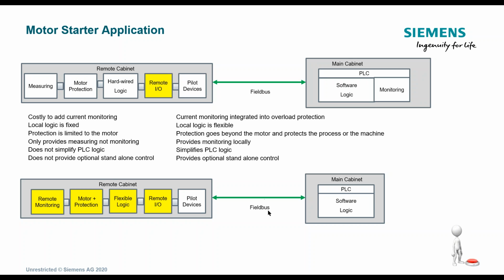What that means is that if this field bus gets cut, the SIMOCODE can continue to run and monitor the system and see if it's healthy and continue to run its last set point that the PLC offered when the field bus was cut, or if the field bus is cut, it can shut down. So this gives you a little bit of small redundancy that if the field bus or this controller goes down, the SIMOCODE can, in its programmable option, continue to run even though it doesn't see the PLC. And that's some of the pluses with the motor management system.